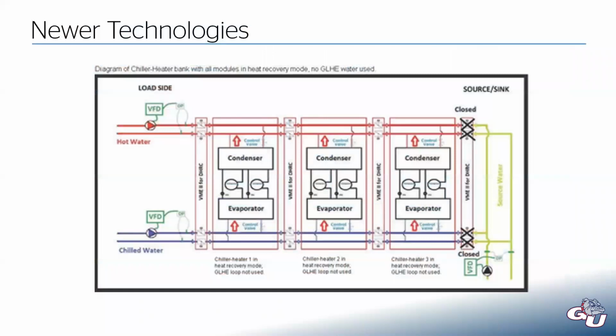And this is more of what the guts look like. So this would be 3, they call them modular chillers, where they basically take 3 smaller chiller modules and slap them together to make one big chiller. But in each one of those modules, you have the evaporator and the condenser. You have your hot water stream coming in on one end, your chilled water stream on the other. And so it pulls heat out of the chilled water side, goes through the evaporator. We have our DX process, and then the condenser rejects that heat into the hot water side.